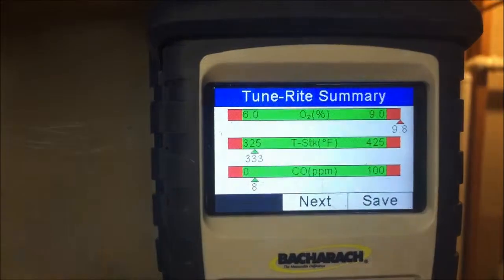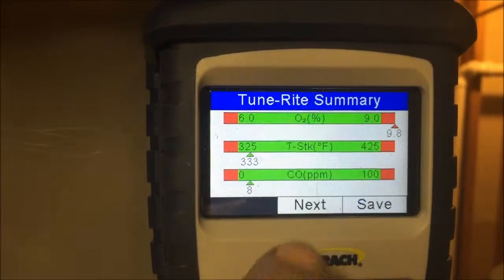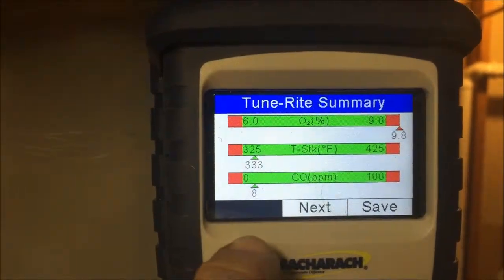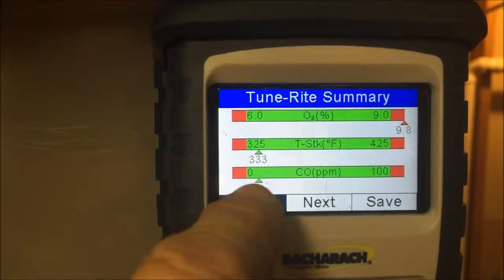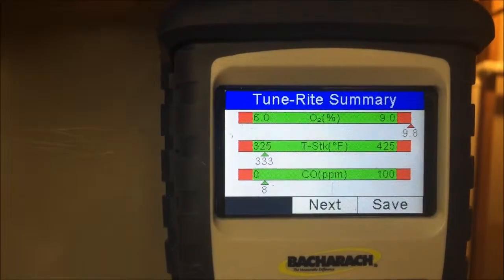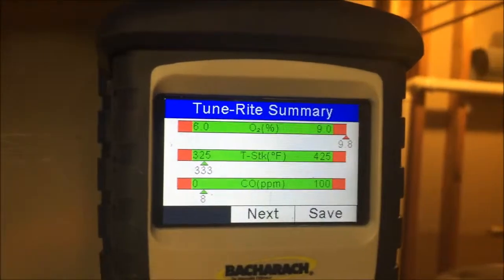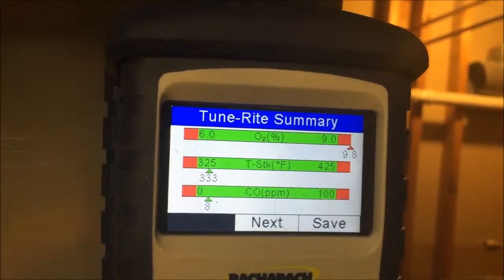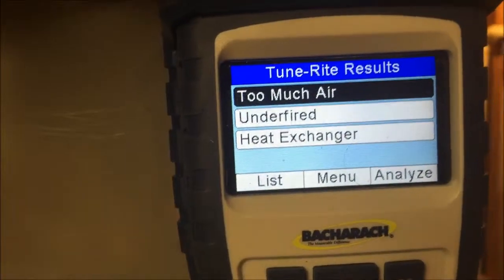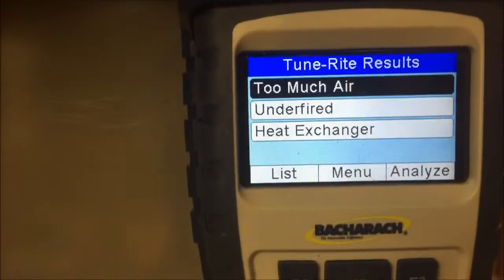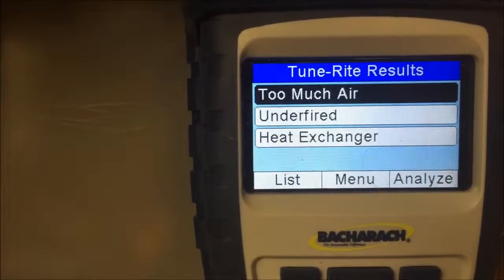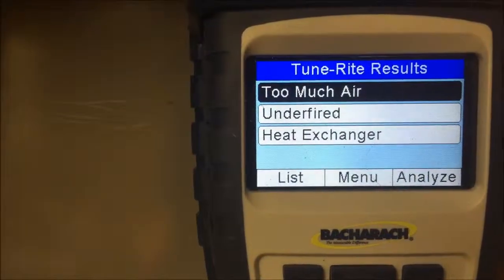9.8. It's red. I'm at the low end of my stack temp, and my carbon monoxide is within range. It says next. So let's hit next. I've either got too much air, I'm under fired, or I've got a heat exchanger issue.